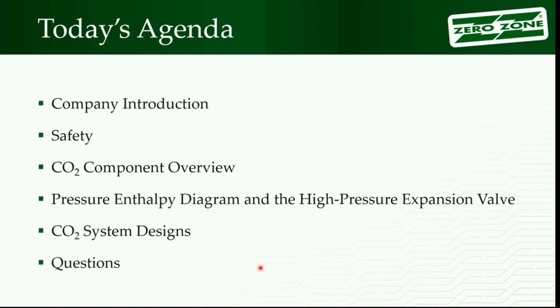So what we're going to talk about today: give you a little background on our company, a couple slides on that. Then we're going to be talking about safety, because safety is important, right? Safety affects you, it doesn't really affect me unless I'm standing there next to you. We'll also talk about CO2 components, making sure we all have the same understanding of the components used in the system, because some of those are what we're going to talk about with how the high pressure valve controls and what it's doing. So we need to know about components to get to the core. And we'll look at the pressure enthalpy diagram with that. Then lastly, we'll finish up, look at some CO2 system issues, or not issues, but some of the safety devices that are put into CO2 systems, and look at some piping and instrumentation diagrams. Again, something you should be familiar with if you're working on these systems, and asking for when you're working on a system.